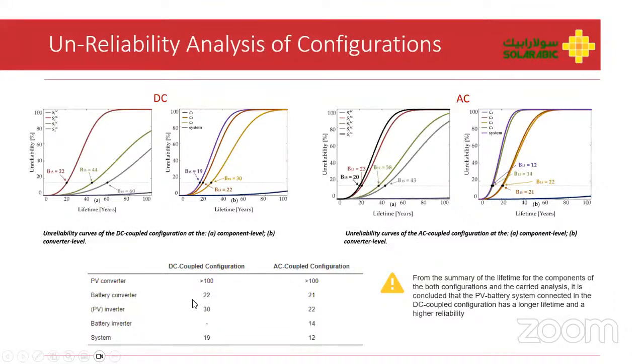But for a battery converter, you get an additional 1 year of lifetime for a DC coupled configuration. Similarly, for a PV inverter, you get 8 more years in a DC coupled configuration. So overall, the system reliability in terms of the performance and the lifespan is 19 years as compared to 12 years in an AC coupled configuration.